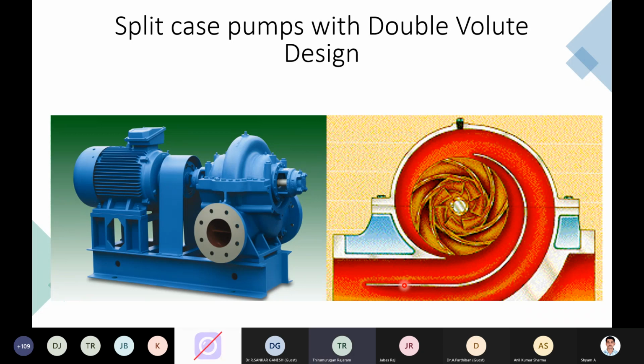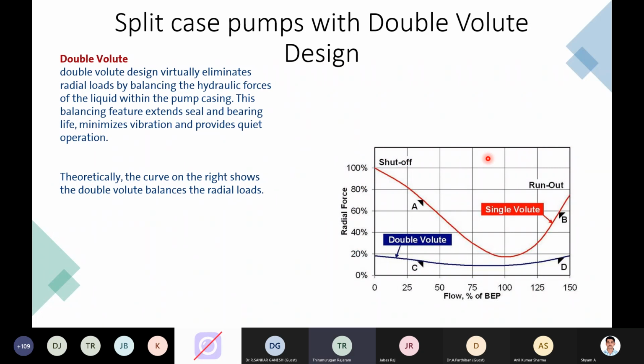And one interesting aspect in the design is that you should consider this double volute design, which will eliminate the radial loads happening on the impeller, because that will avoid the proper rotation of the impeller, and a wear and tear situation can arise. So the double volute design is a common one in all split case pumps, which can be taken up here. So some design reasons for having a double volute instead of a single volute: eliminating the radial loads by balancing the hydraulic forces of the liquid within the pump casing. So this enables more adaptation of running the pump at the designed parameters. So once you eliminate much of the radial load, you are almost saving the pump internal parts from any damage. Okay.